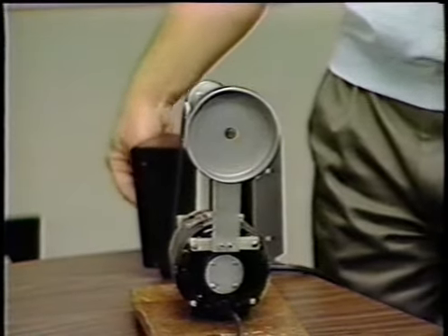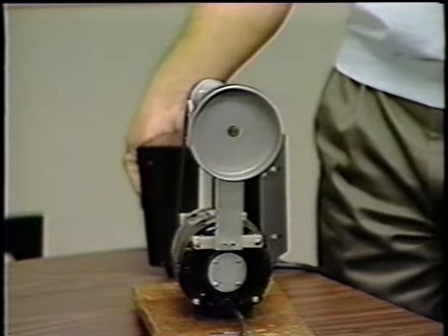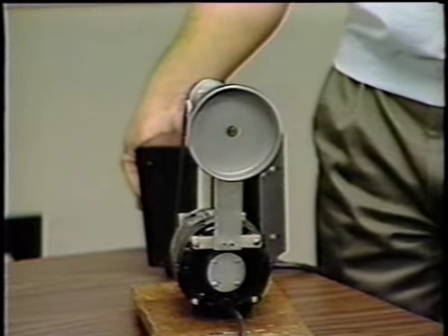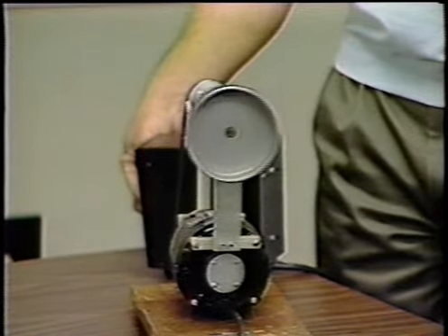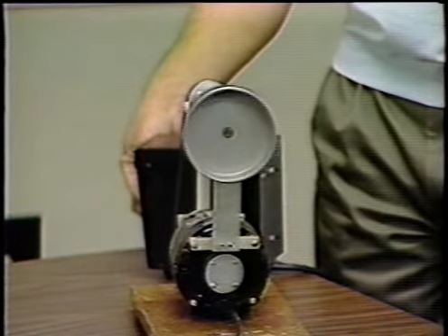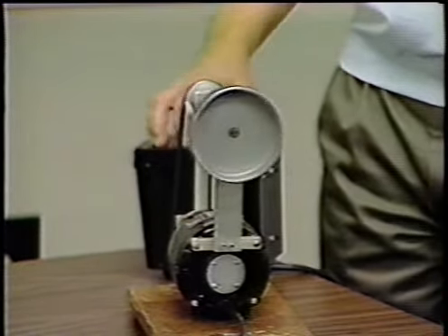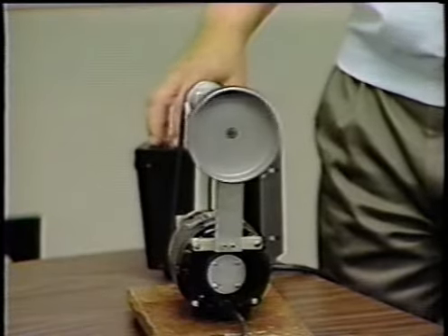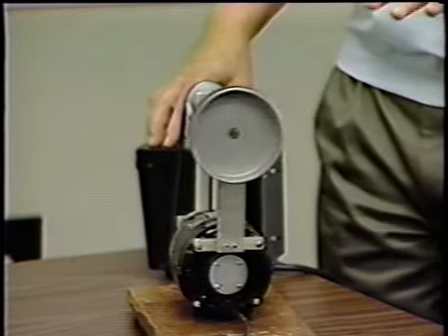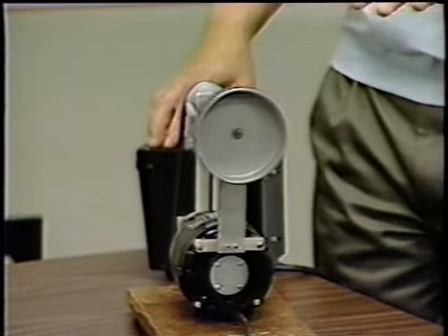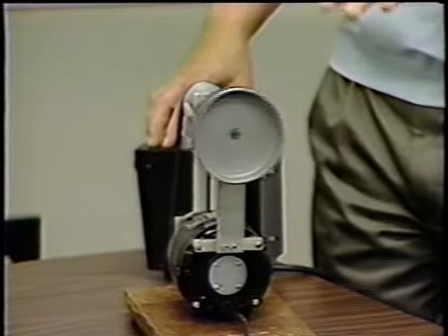What I'm going to do here is simply slow down this motor demonstrator. I'm going to reduce its exciting force frequency, and as you'll see, we'll reach a certain point where the vibration will be tremendously amplified. I think it's obvious that what we've done here is reach a point where the vibration is extremely high. It's much, much higher than it was at any other operating speed. And again, all we've done here is to simply adjust the exciting force frequency to make it equal to the natural frequency of this particular element.